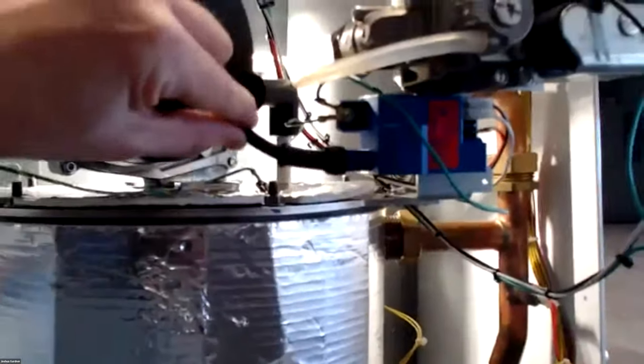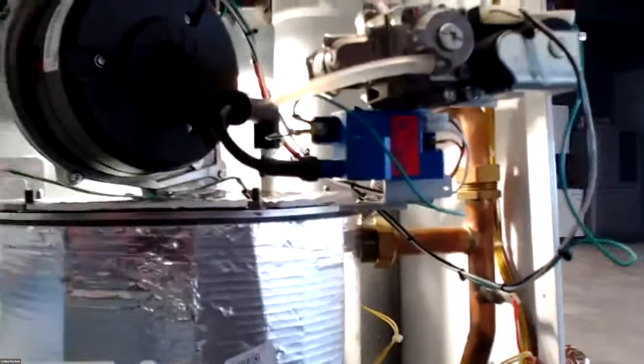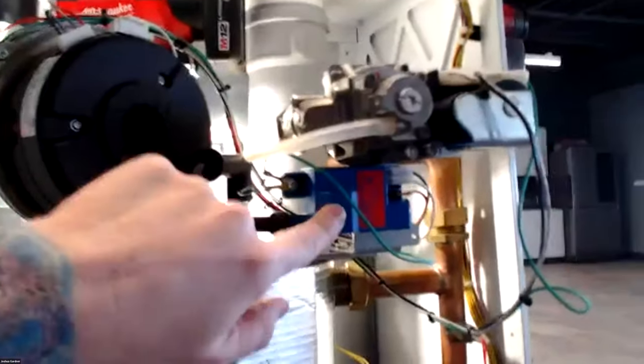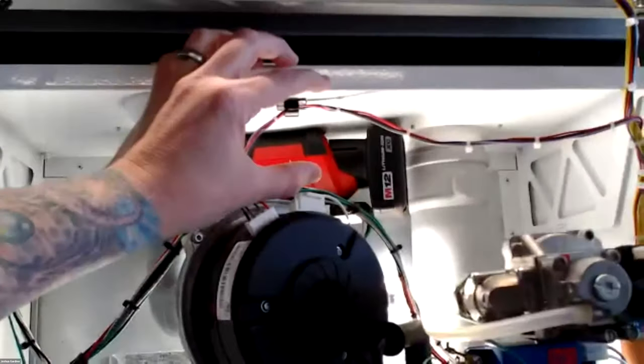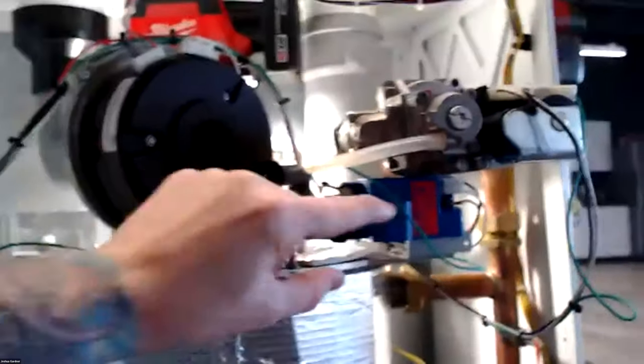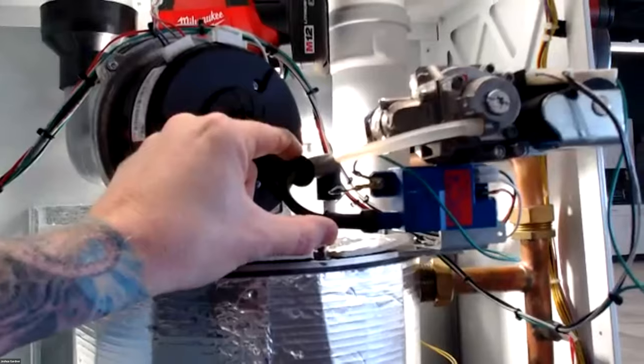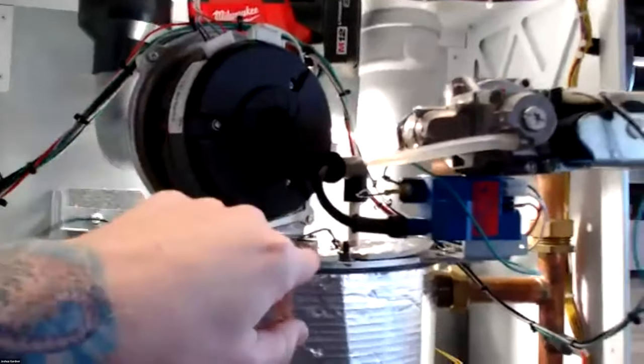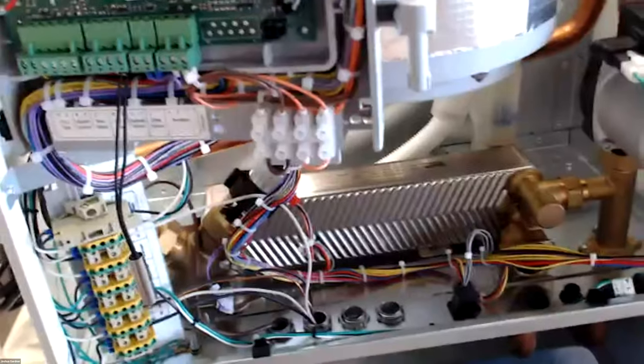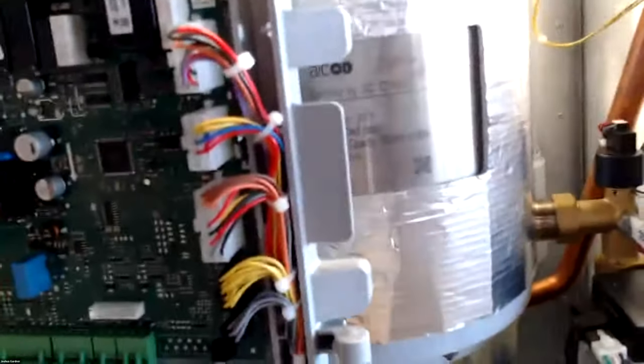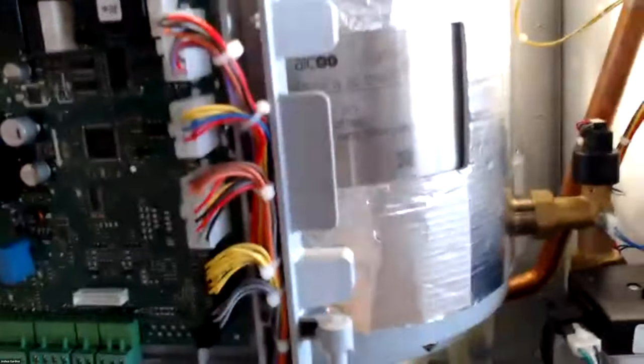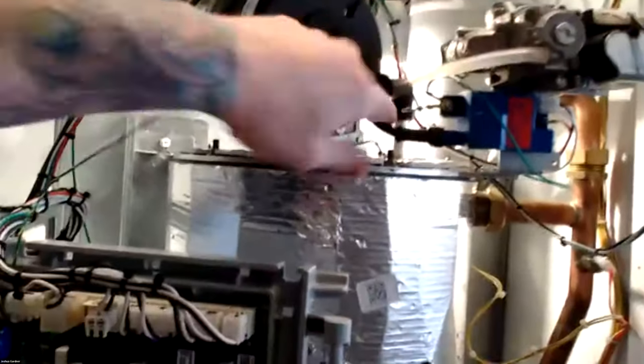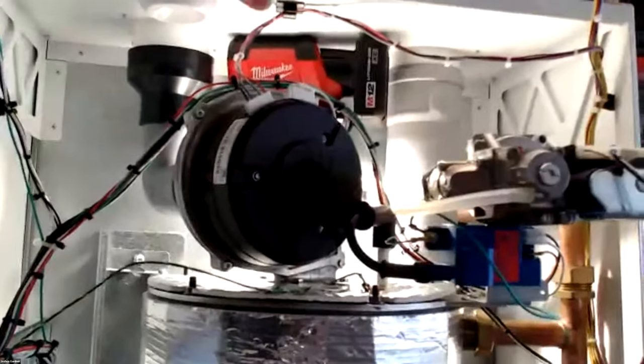Then your ignition lead. One thing we changed is on the floor boilers, we moved our ignition transformer from up here down to underneath our gas valve. So this ignition lead is shorter on this one. So that's different. Same igniter, same ignition module, same gas valve, same boards, same flat plate, same pump, all those components are the same. So if you purchase one of the service kits, you essentially have everything for this floor boiler. Same fans, you just have the different wiring leads and different control display.